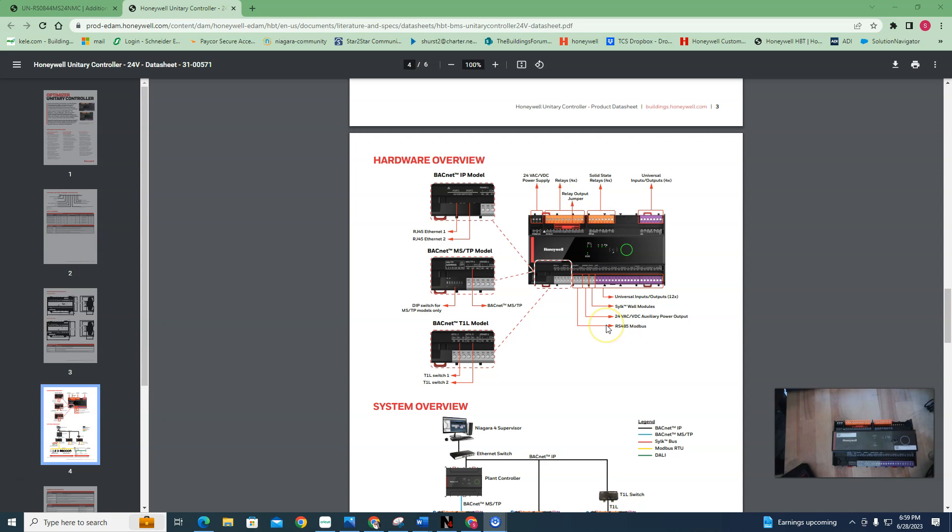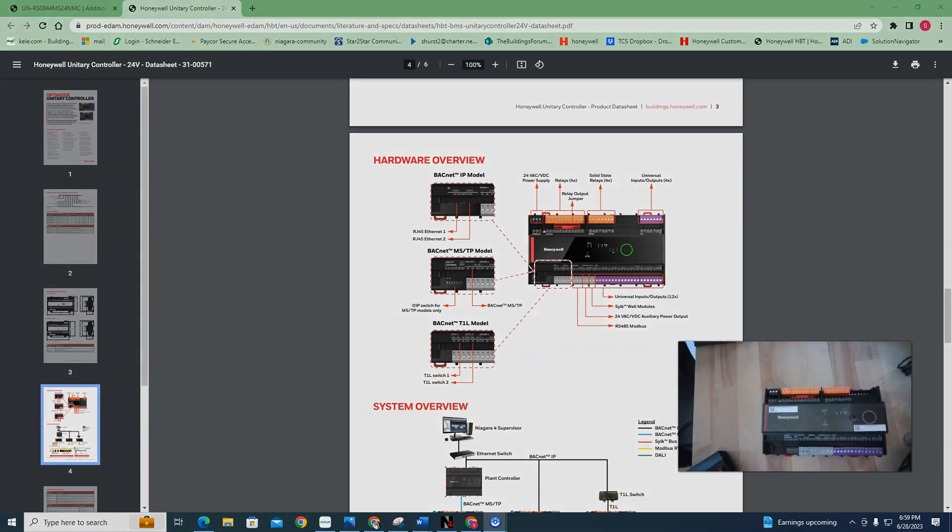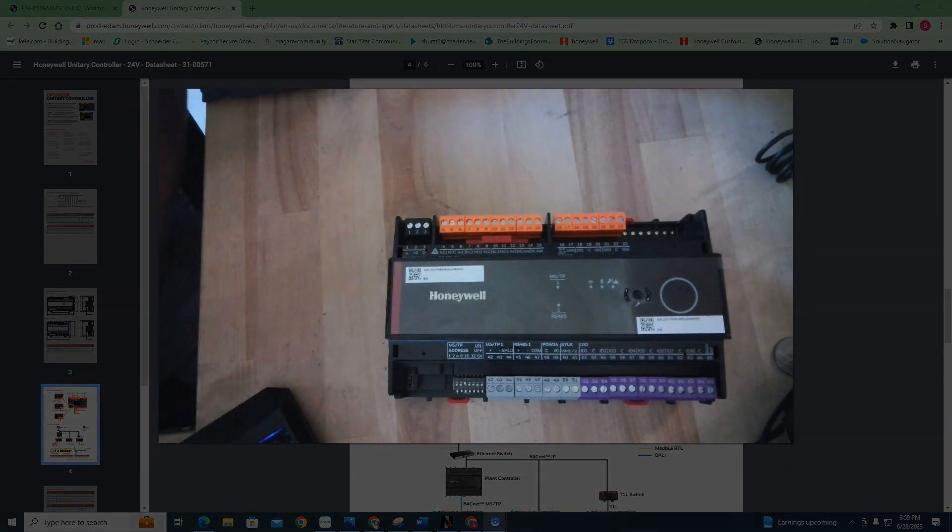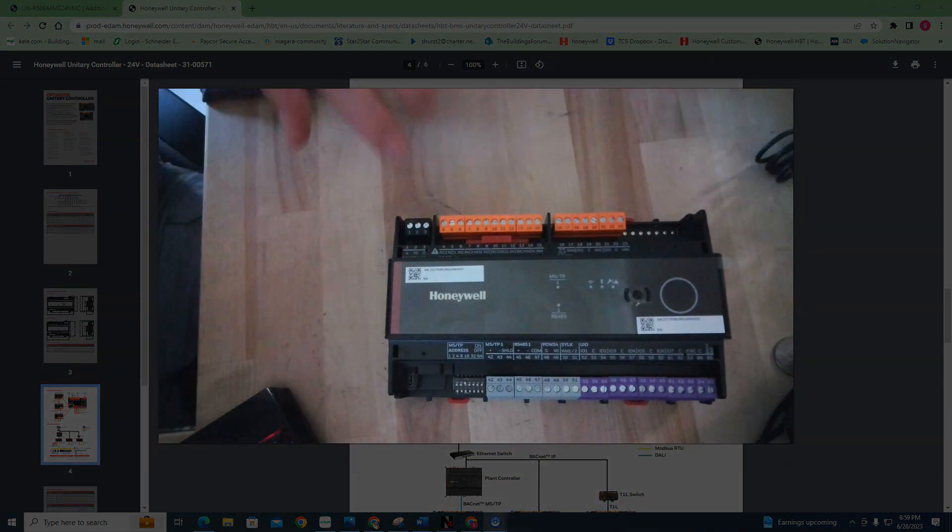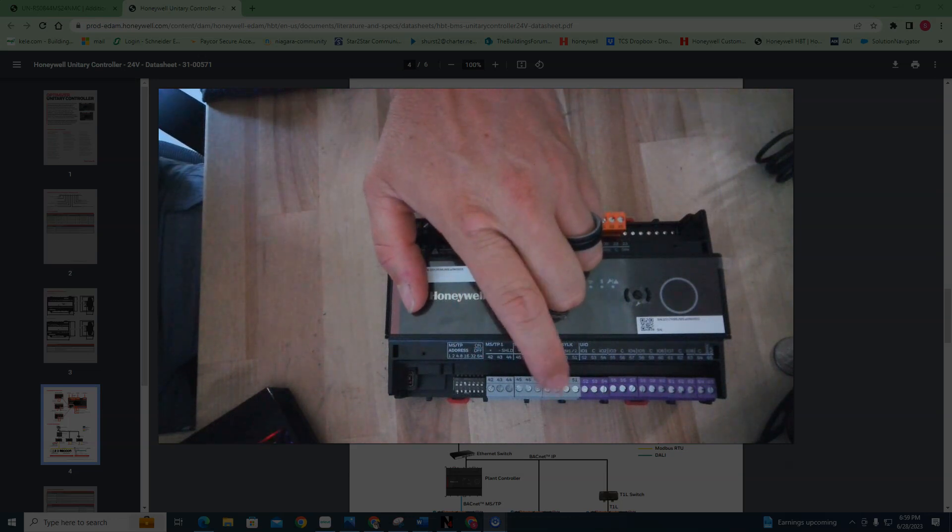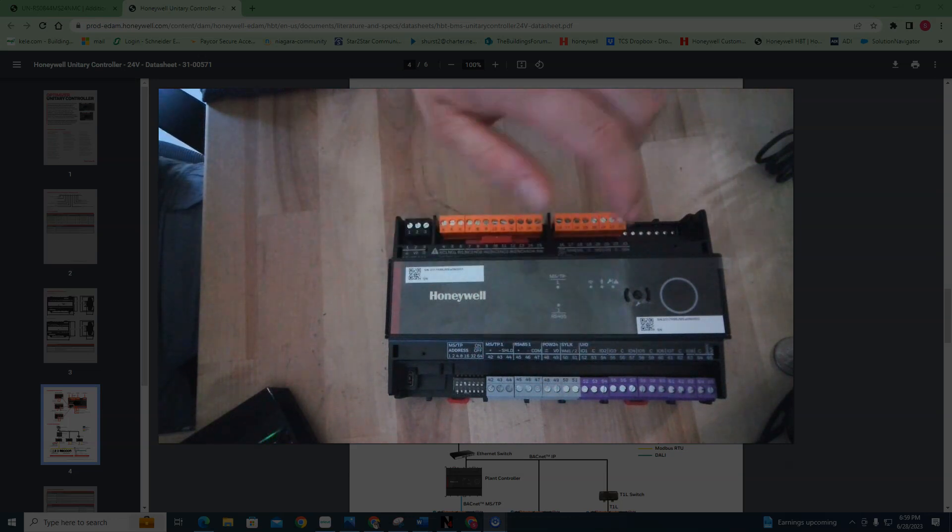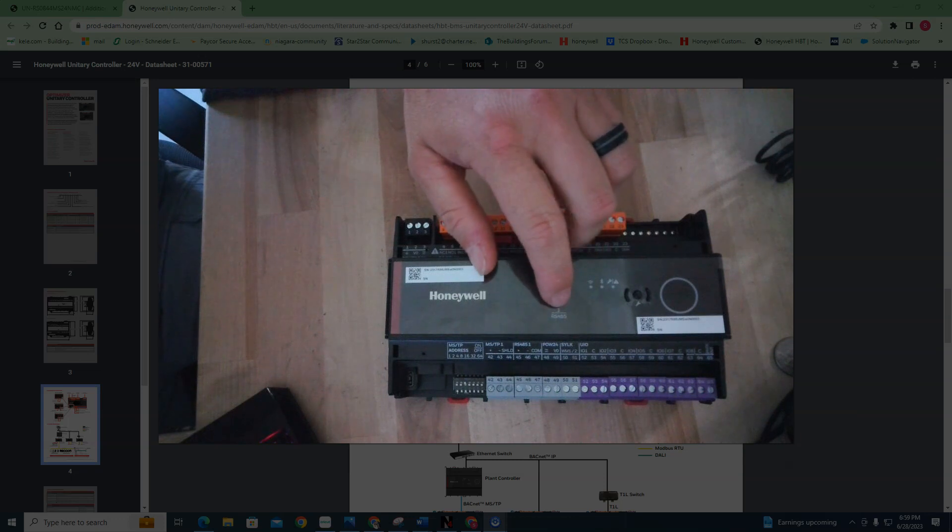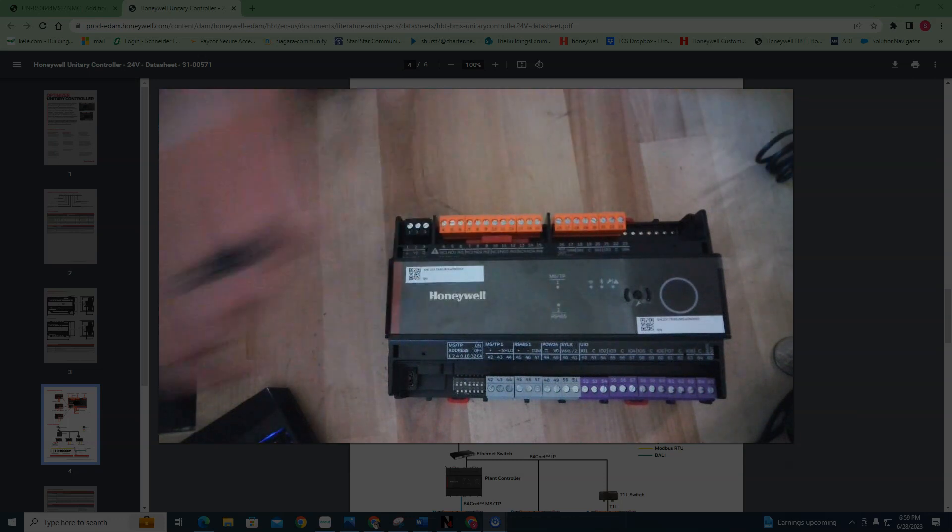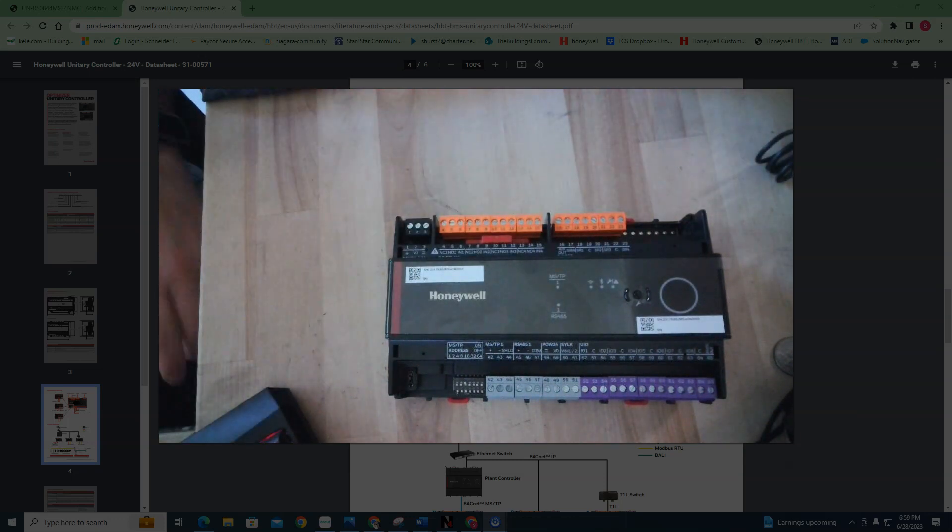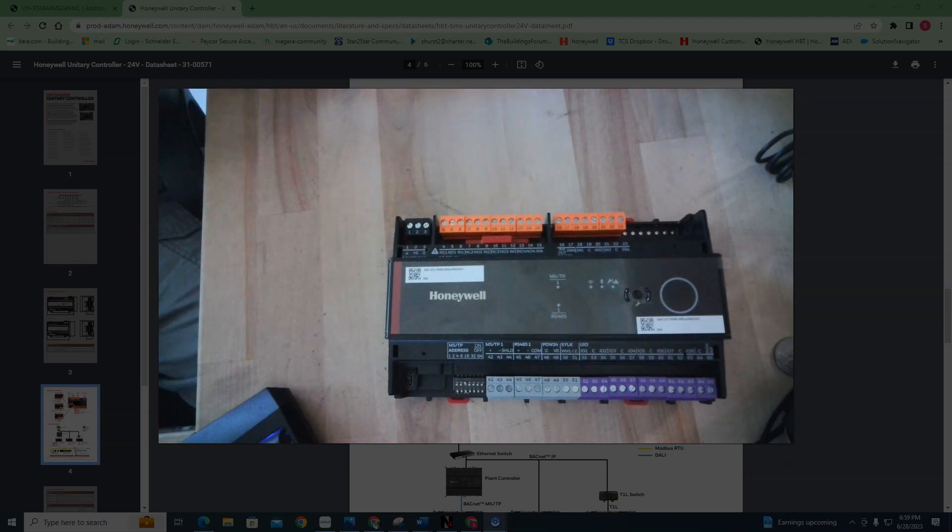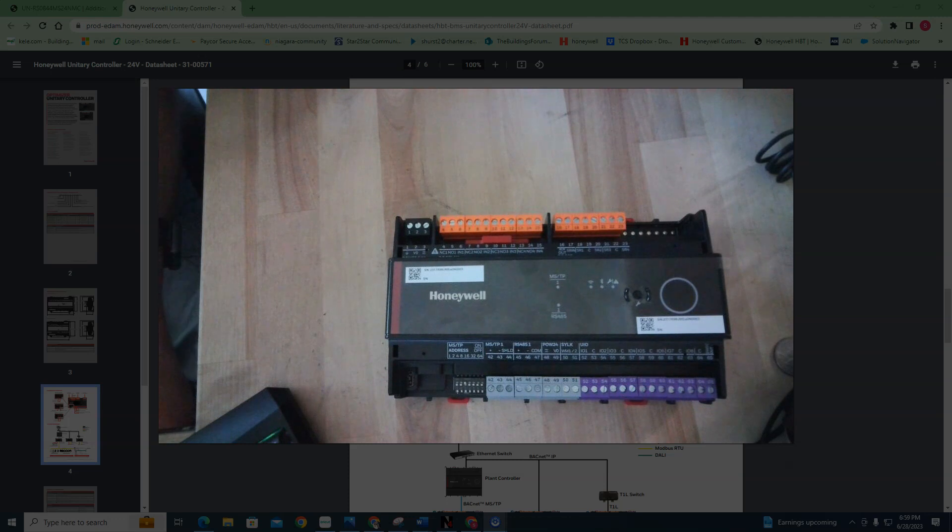Also on all the new Honeywell controllers that they're putting out, you have Sylk bus and you have an extra 485 modbus port on these guys. So I can show you that right here. You got your MSTP, but right next to your MSTP is your second RS485 for modbus.